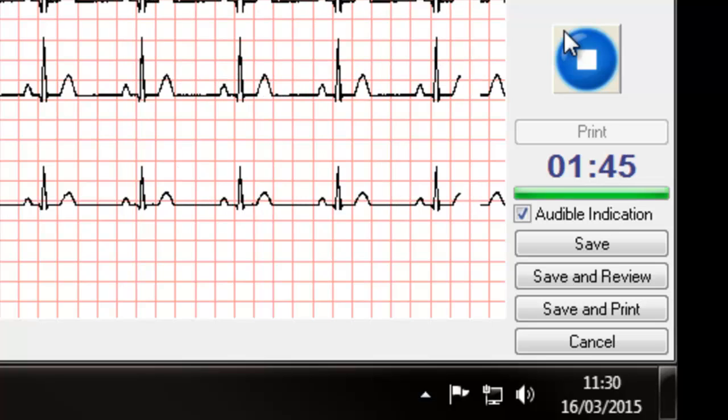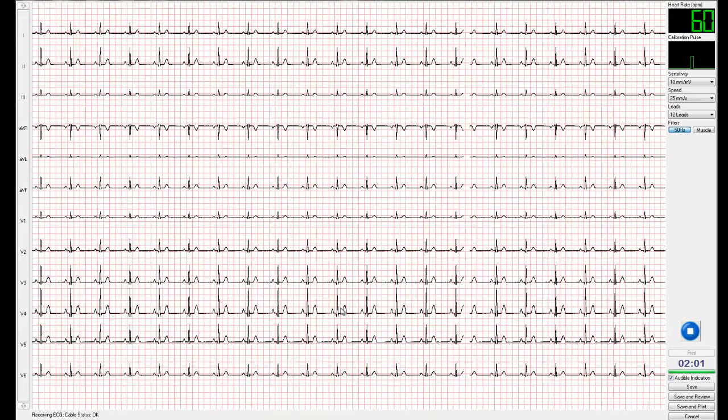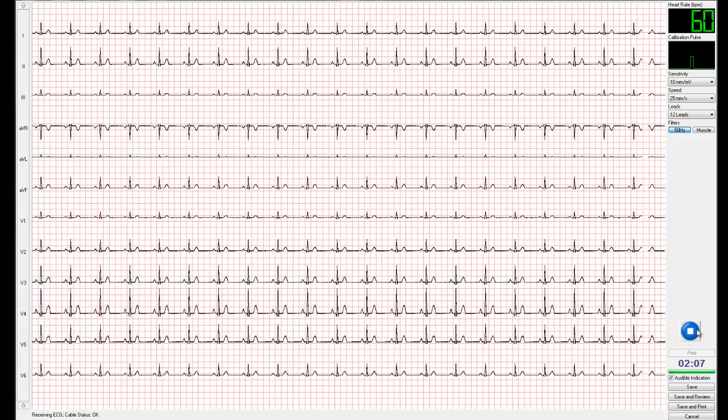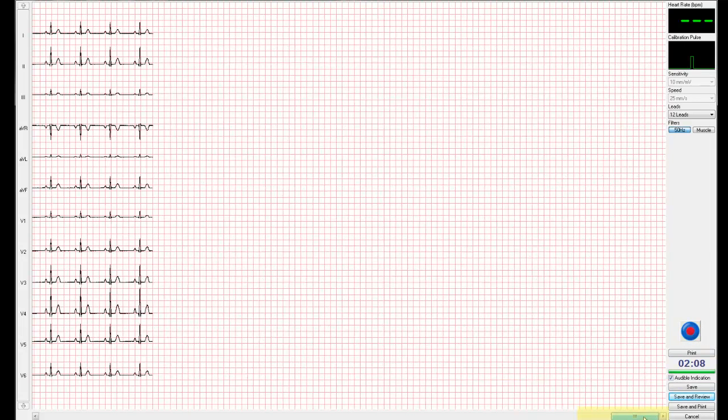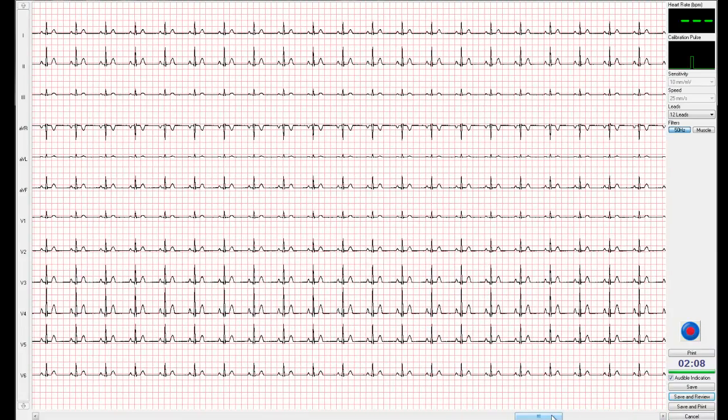Another useful feature is the Stop button, available during ECG monitoring. If you had noticed some unusual rhythm activity on screen but hadn't managed to press the Save button in time to capture it, simply press the big blue Stop button. This will stop the real-time ECG monitoring and a scroll bar will appear at the bottom of the screen. Moving the scroll bar will allow you to scroll back by up to 15 minutes of the monitoring period, enabling you to display a 10-second segment on screen to form the ECG report.